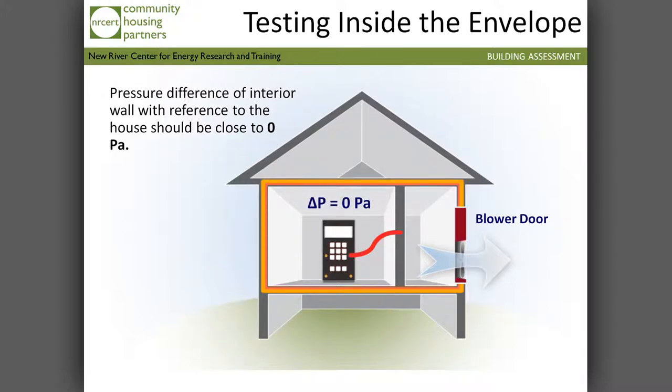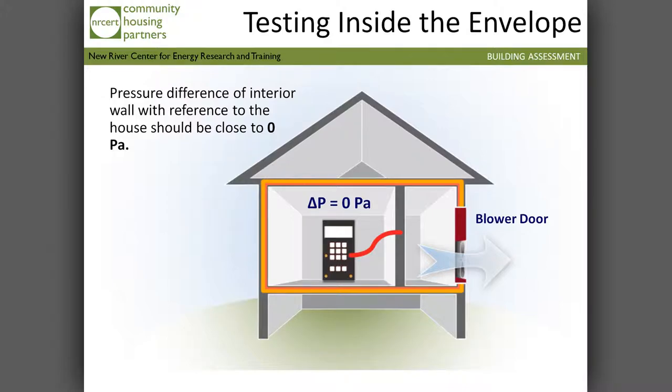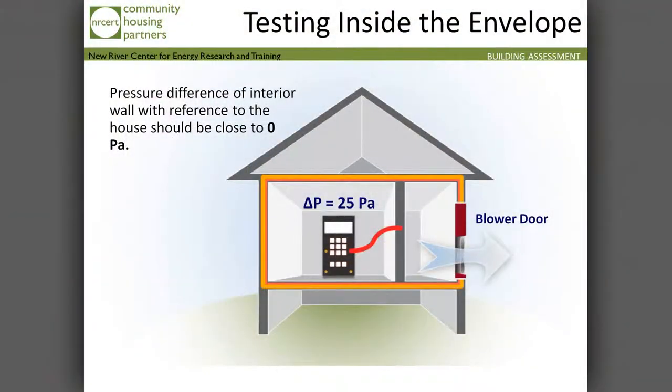When we're testing inside the envelope, we should see zero. If this is a complete thermal and pressure boundary — no holes in the top plate, electrical and plumbing penetrations have been sealed — then we should see zero or close to it. When you get below five, you're doing pretty well. You don't want to focus a lot of attention on really small numbers; look for the larger numbers initially.